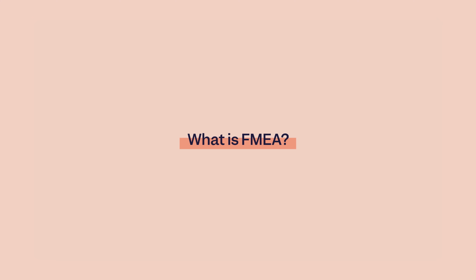In this course, you will learn how to conduct the risk analysis according to ISO 14971:2019, using failure modes and effects analysis, FMEA. The failure modes and effects analysis is a systematic approach for identifying the ways or hazards in which an item, like a medical device or process, might fail its intended objectives and the effects of such failures. The ways in which a product or process can fail are called failure modes. So, the purpose of FMEA is preventing process and product problems before they occur.